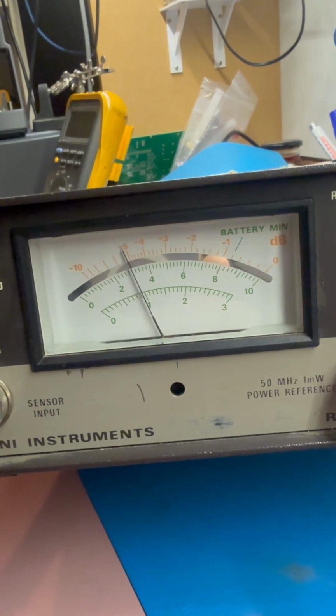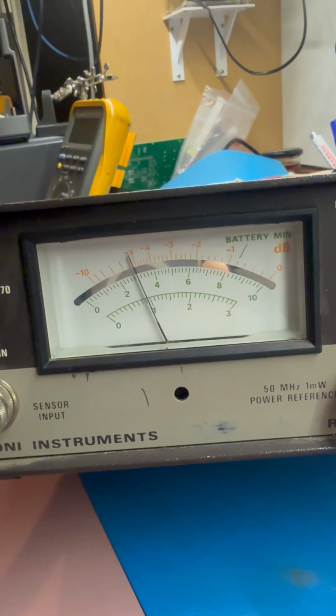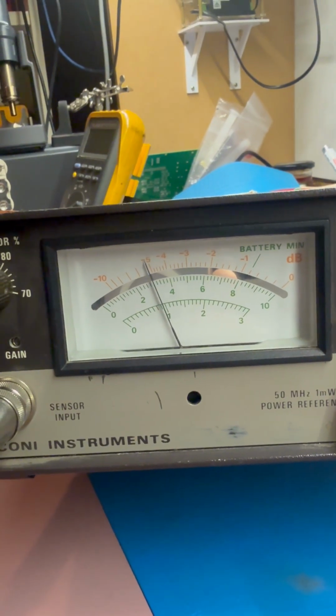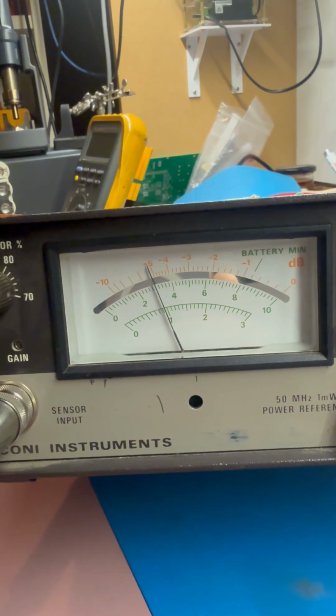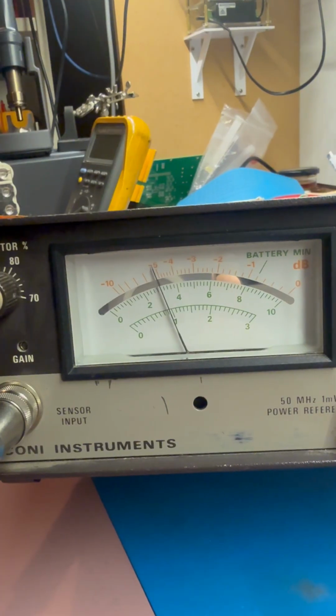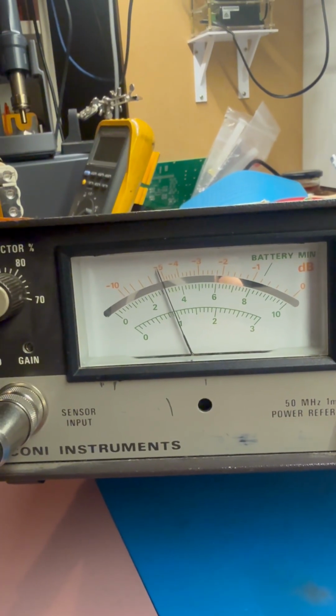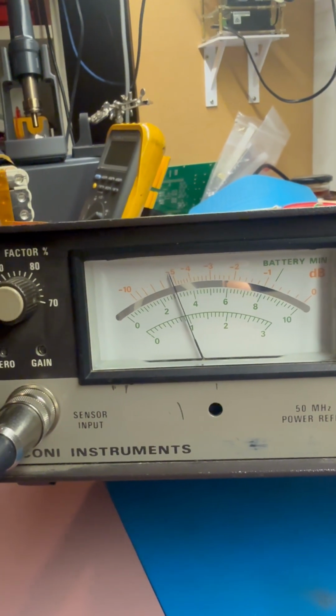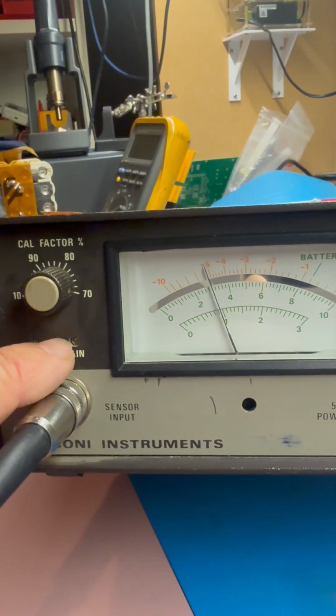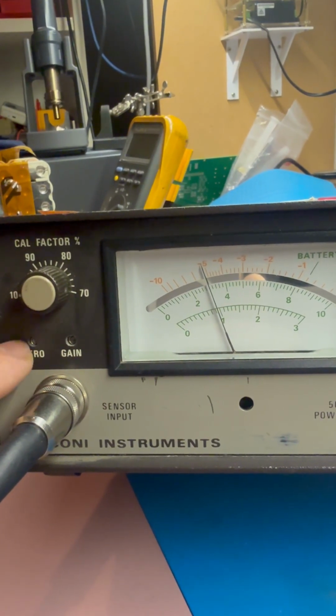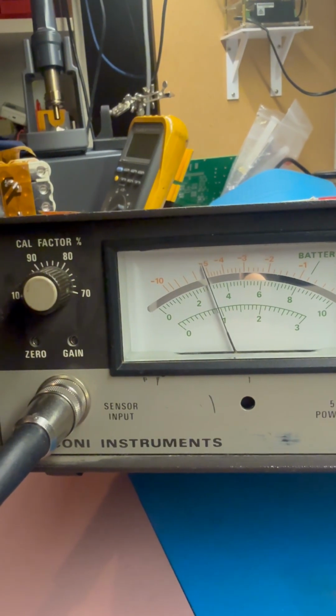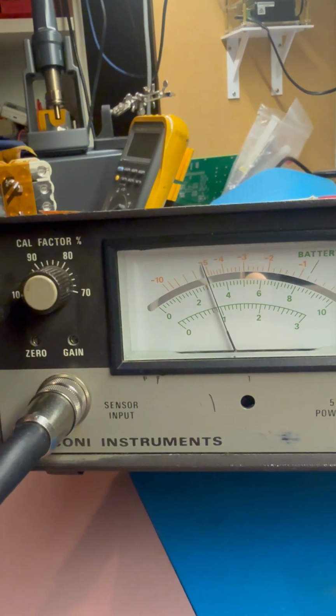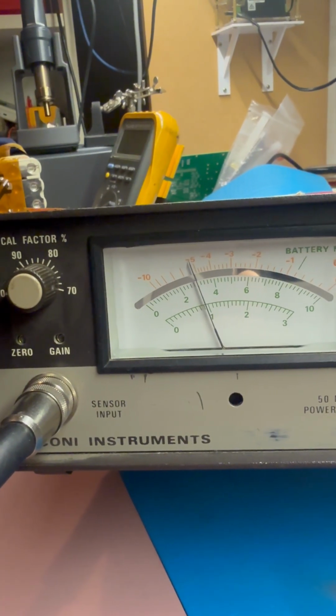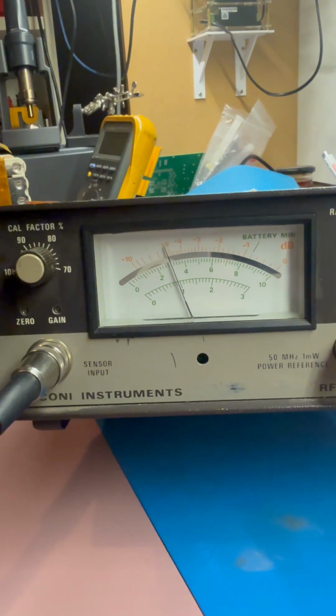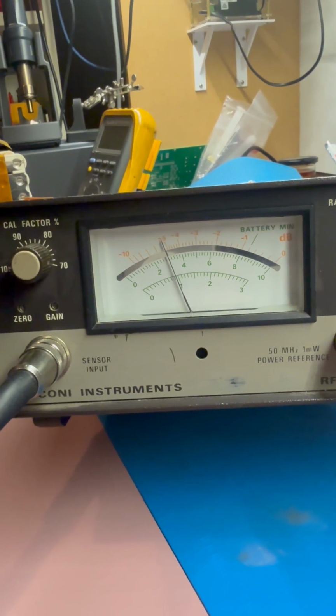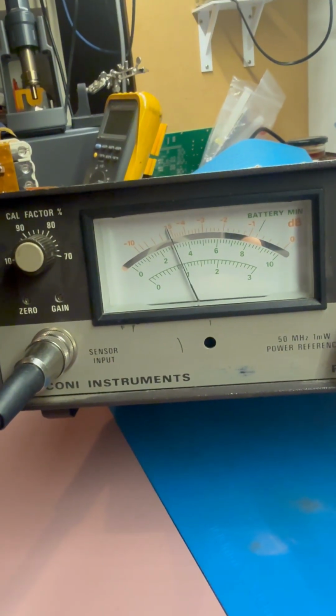The calibration on this instrument is probably the most tricky part. If I was to put it back to 0 or put it back to full on this range, I'd probably have to recalibrate again. The 0 and the gain here, you need to go through them a couple of times before everything is right, and have it all warmed up. And I've started this cold, so all the equipment is still warming up. Anyway, the sensor, as far as I can see, is working okay.